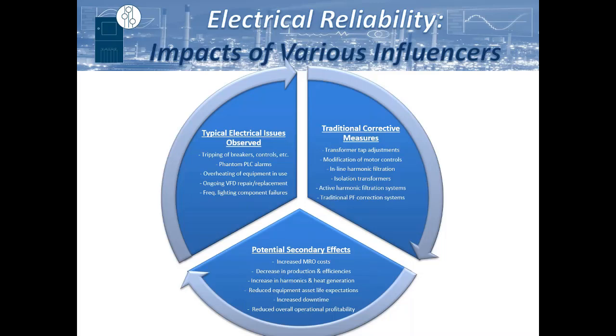Modification of motor controls, so adding additional limiting factors that are acquired over years of experience, and understanding that if we lower these current settings or input settings, that'll ensure we minimize the interruptions. There are also additional external solutions, such as inline harmonic filtration or isolation transformers, active harmonic filtration systems, and even traditional power factor correction systems. But all of these have an impact on the network as well, some of them beneficial, some of them not so much.